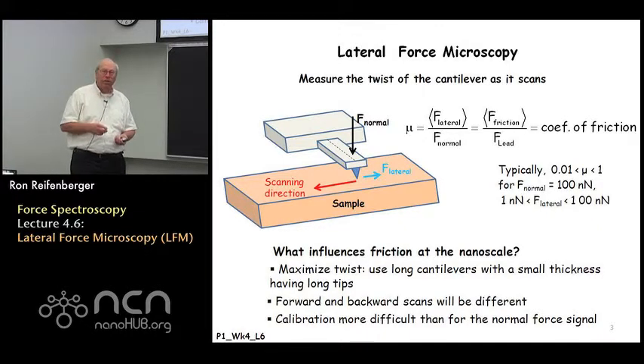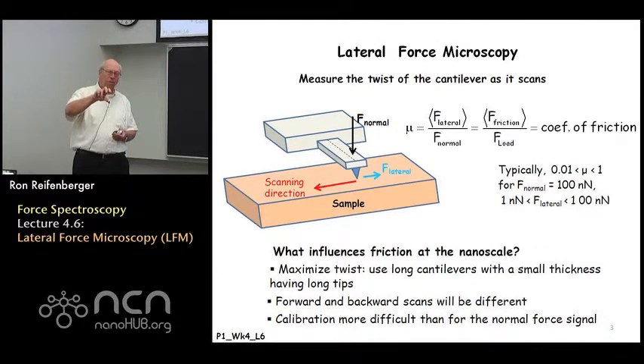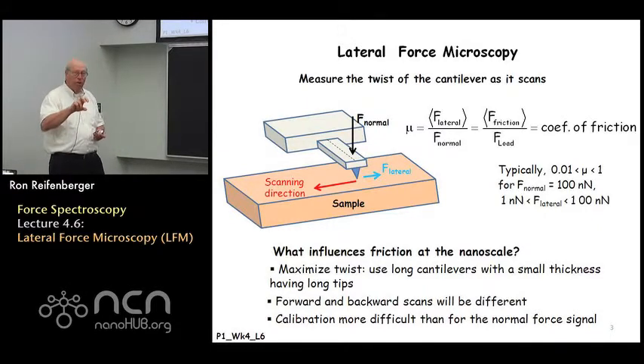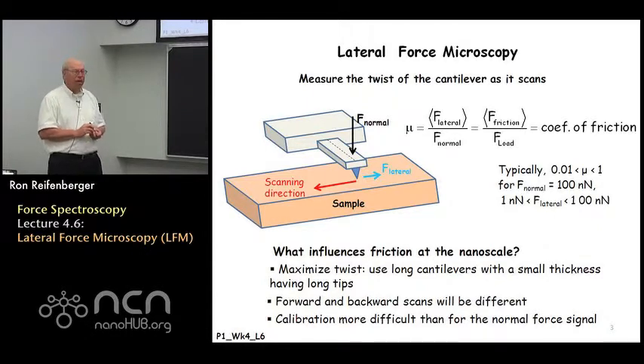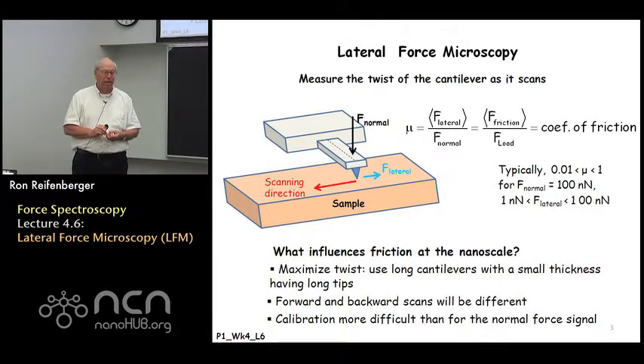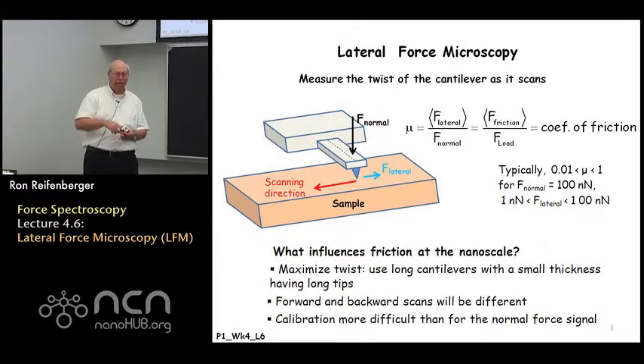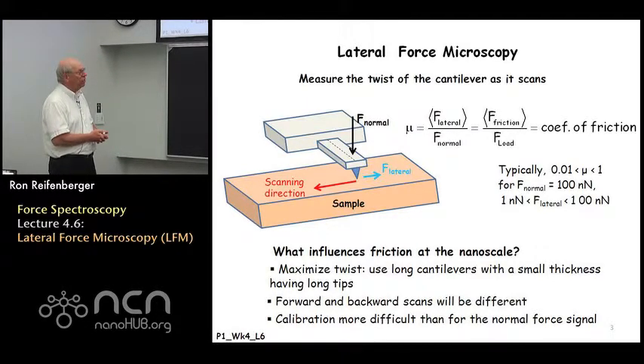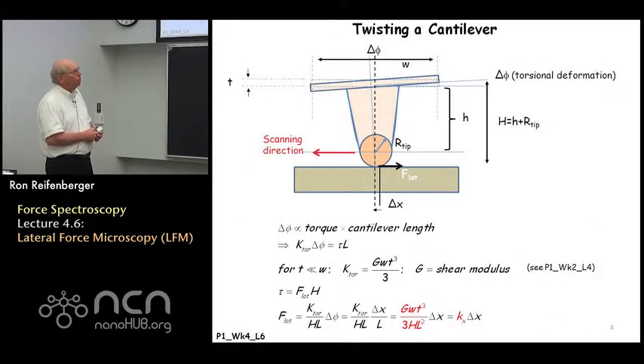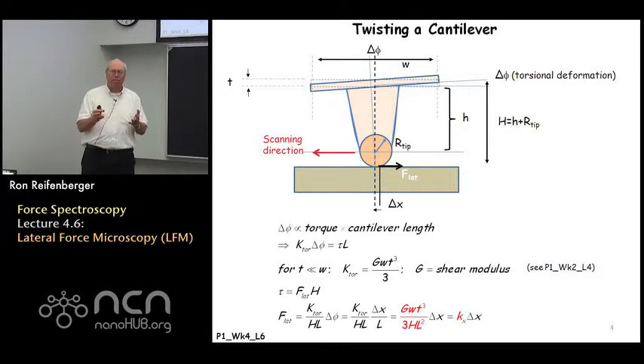To maximize the lateral force signal, the lateral force causes the cantilever to twist through a small angle. To optimize that twist and make it as large as possible, you typically want to use long cantilevers that are very thin and have long tips. The question then becomes how do you calibrate the twist of the cantilever with the lateral force that produced it — that turns out to be an interesting and challenging experimental problem.